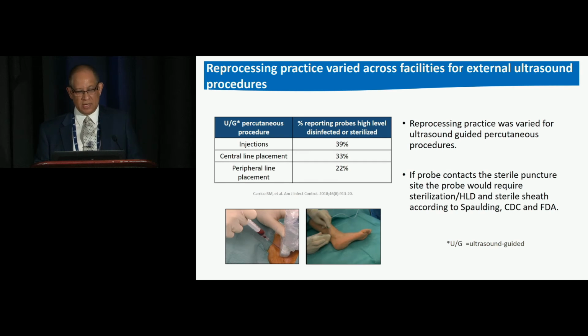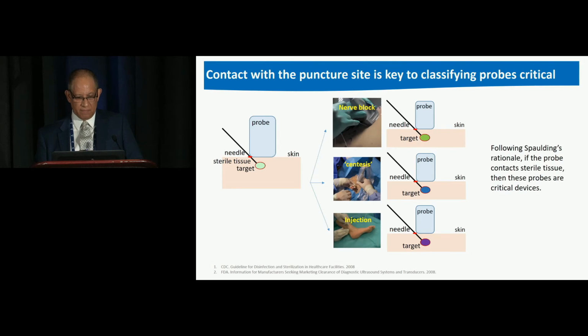And I remember when I was, if you want to say, a young practitioner, I never even thought twice about that. I was so much more concerned about the kits that they were using and how they prepped the skin, et cetera. And I never thought about the ultrasound that they were using. Take a look at some of the responses nationally about this. So reprocessing practice was varied for ultrasound-guided percutaneous procedures. And if the probe contacts the sterile puncture site, the probe would require sterilization or high-level disinfection and a sterile sheath, according to Spaulding, the CDC, and the FDA.